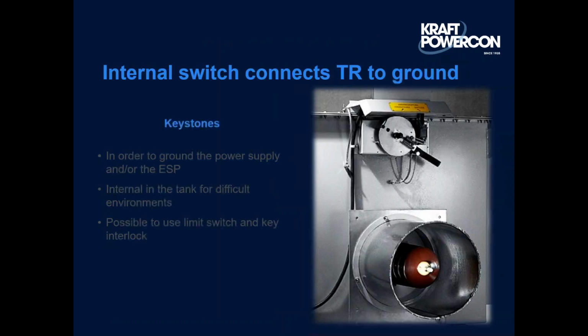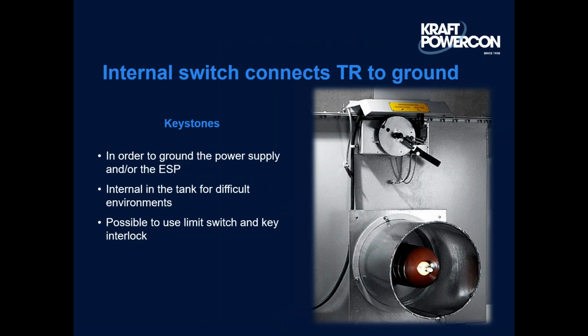Next slide. Now we get into safety, where we have our different switches on our TR sets. A ground switch is needed to ground the precipitator, and most of this design is for personnel protection. So we have an internal ground switch. What's nice about the Kraft Powercon TR set is we have a sight glass that you can actually see the positive contact of that switch. Many TR sets out there with internal switches don't have that sight glass, so it's really a guess if it's grounded or not, which doesn't give full safety. It doesn't bring the potential to zero.